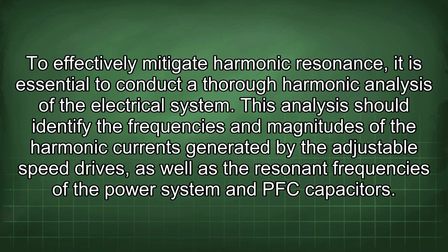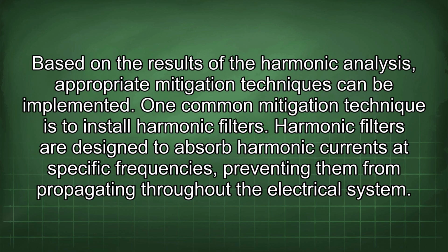To effectively mitigate harmonic resonance, it is essential to conduct a thorough harmonic analysis of the electrical system. This analysis should identify the frequencies and magnitudes of the harmonic currents generated by the adjustable speed drives, as well as the resonant frequencies of the power system and PFC capacitors. Based on the results of the harmonic analysis, appropriate mitigation techniques can be implemented. One common mitigation technique is to install harmonic filters. Harmonic filters are designed to absorb harmonic currents at specific frequencies, preventing them from propagating throughout the electrical system.